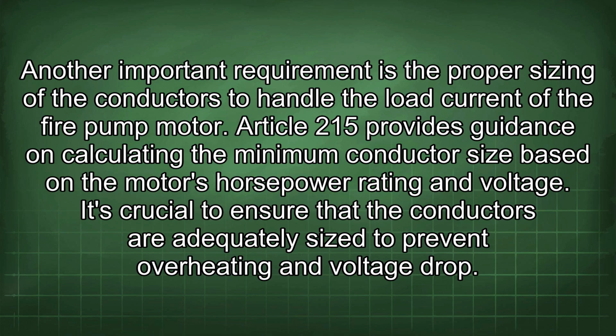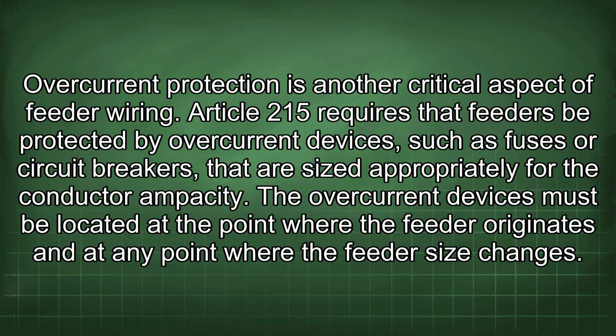Another important requirement is the proper sizing of the conductors to handle the load current of the fire pump motor. Article 215 provides guidance on calculating the minimum conductor size based on the motor's horsepower rating and voltage. It's crucial to ensure that the conductors are adequately sized to prevent overheating and voltage drop. Overcurrent protection is another critical aspect of feeder wiring. Article 215 requires that feeders be protected by overcurrent devices such as fuses or circuit breakers that are sized appropriately for the conductor ampacity. The overcurrent devices must be located at the point where the feeder originates and at any point where the feeder size changes.